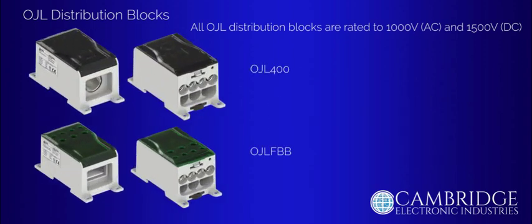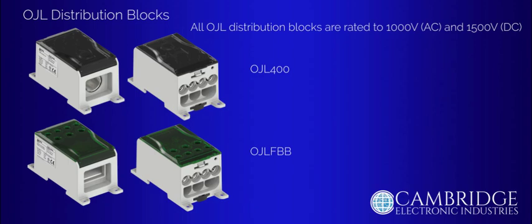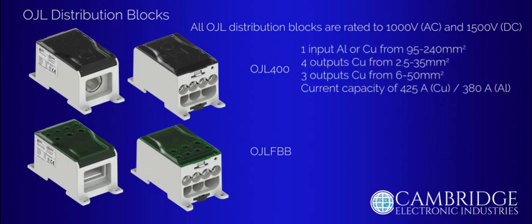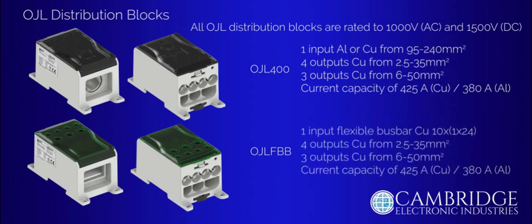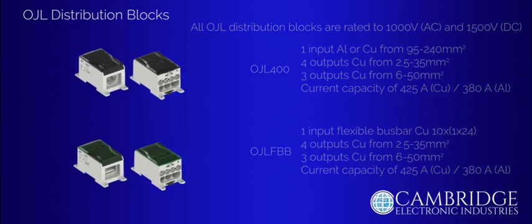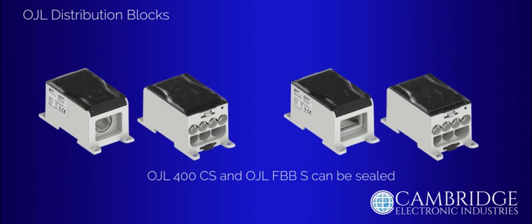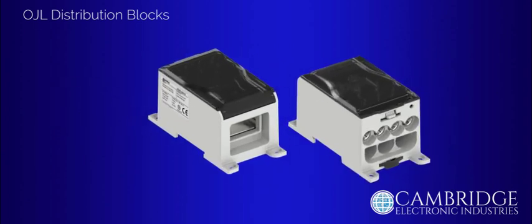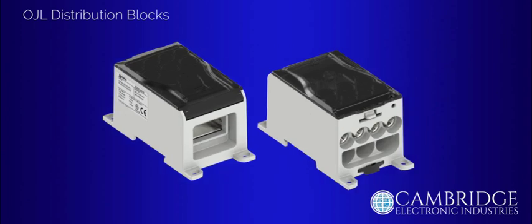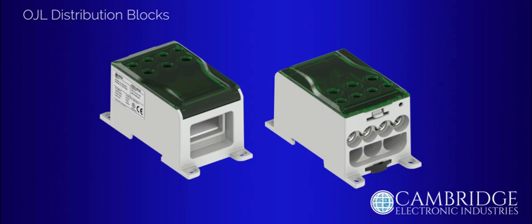OJL 400 and FBB offer the largest current capacity of the OJL distribution block range. The OJL 400 has a single copper or aluminium cable input, whilst the OJL FBB is designed for a flexible copper busbar input. Both connectors have current ratings of 425 amps for copper inputs and 380 amps for aluminium inputs. The current is distributed through 7 outputs, which are in 2 different cable sizes. Both the OJL 400 and the FBB versions also have the option of sealing the cover of the block. This is only available in both models with a transparent black cover. The standard models of OJL 280, 400 and FBB are available with black, blue or green transparent covers, and all models can be screw or DIN rail mounted.